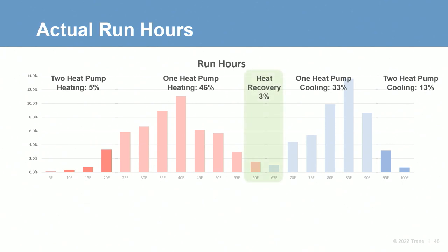The last bucket is the potential heat recovery operation. At only 3% of the total run hours, this bucket has the lowest usage. Without some kind of process load like a data closet, the simultaneous operating hours for this application are extremely low. Having units capable of heat recovery would provide very little in terms of financial payback for a project like this.